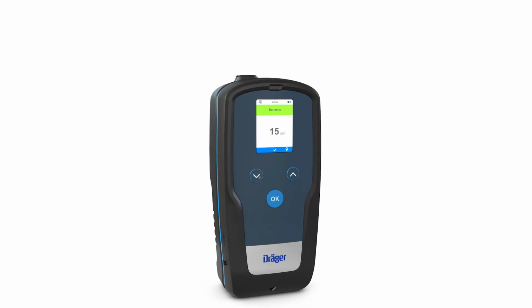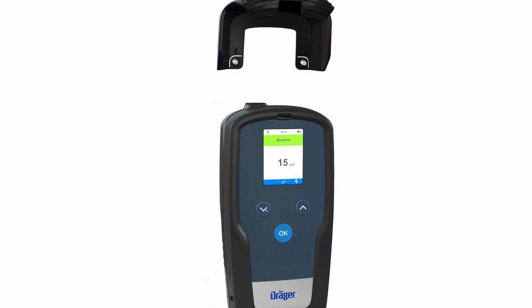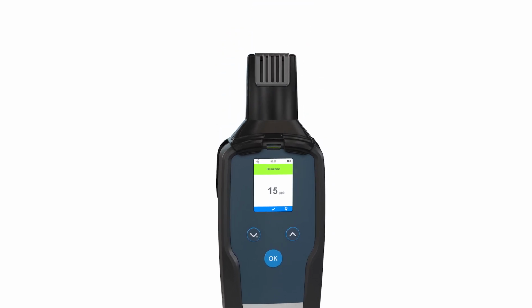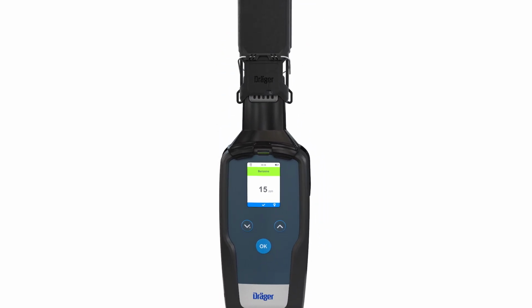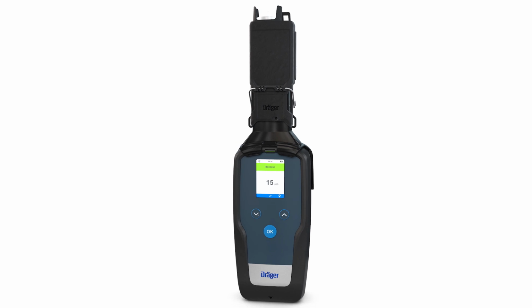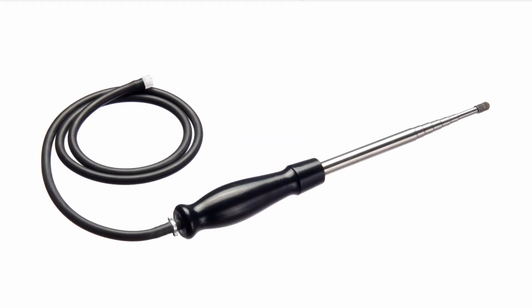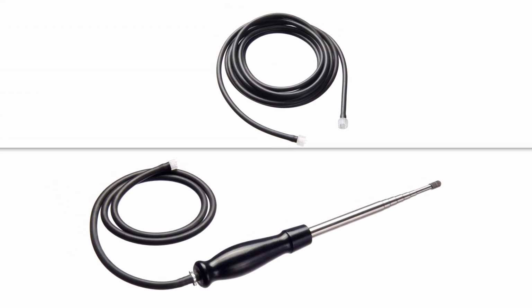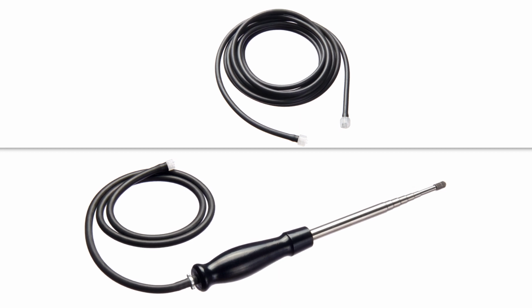When testing confined spaces like ducts, shafts, and containers for safe entry, the device can be connected via a coupler to the Dräger XAM pump. A range of probes and hoses in lengths of up to 45 meters allow you to perform tests in hard-to-reach places.